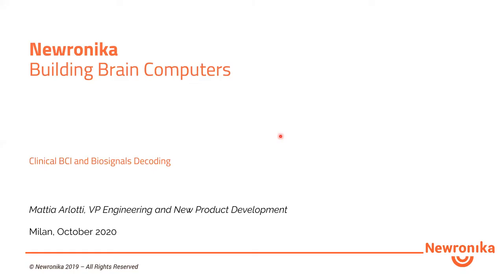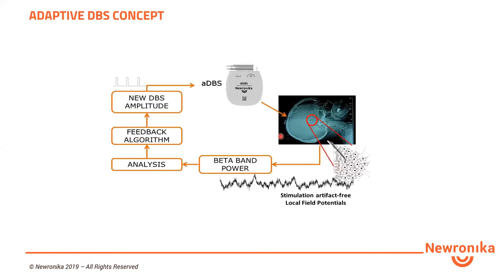My role is to lead the technological development of brain-computer interfaces and implantable brain-computer interfaces in Newronika, together with the CEO. We are targeting Parkinson's disease and the application of adaptive brain stimulation, which is based on an implantable pulse generator able to record local field potentials, clean them from stimulation artifacts, process them, extract a biomarker of the patient's clinical state, and then adapt the stimulation parameters in real time.